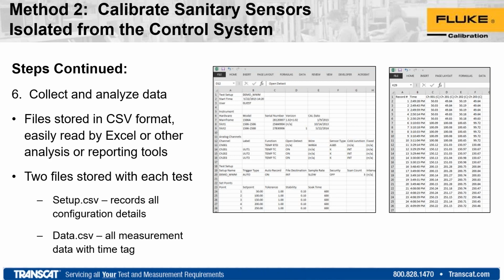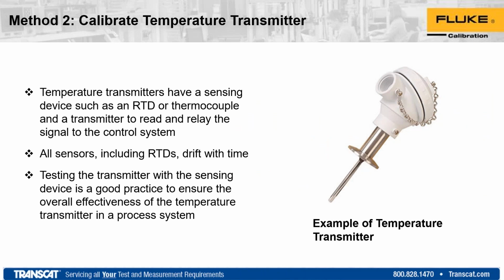All right, so continuing on with this method 2 type system, where we've now integrated a readout device like the 1586, we'll show you how to use a temperature transmitter. The process is fairly the same, only instead of outputting the resistance or millivoltage, the transmitters typically output a 4 to 20 milliamp signal that's interpreted. So basically, if you're using a 0 to 100 probe, 0 would be considered 4 milliamps and 100 would be considered 20 milliamps.